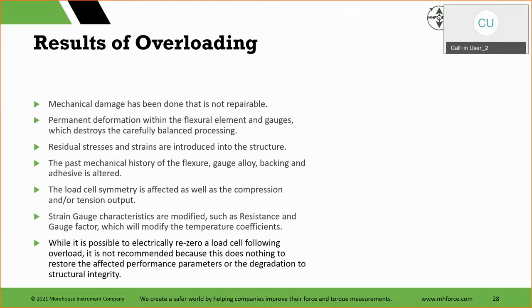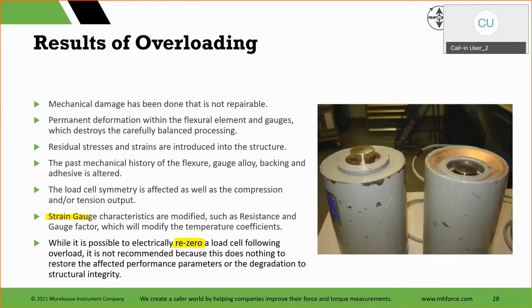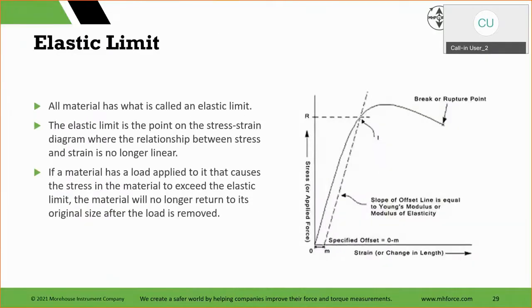Strain gauge characteristics are modified, such as resistance and gauge factor, along with the temperature coefficients. That's typically the first to go, right here, the temperature. And while it is possible to electrically re-zero, such as with a meter, just reprogram my meter, there may be other things going on that make it not fit for use, so it should be checked out. It is not recommended because this does nothing to restore the affected performance parameters or the degradation to structural integrity. So again, I overloaded something. If I'm looking at Young's modulus, I took it past the elastic region, and now I've altered the properties. And speaking of Young's modulus, here it is.